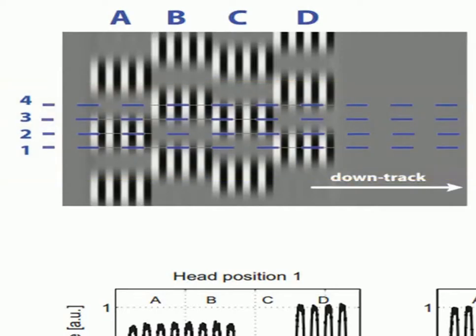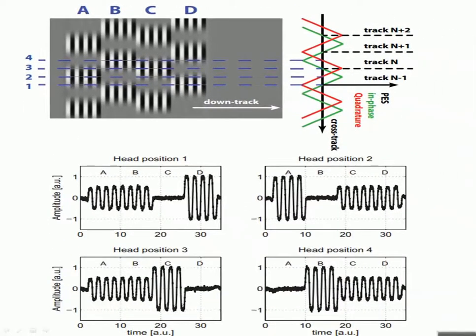Notice that when the head is on track, positions 1 and 3, the bursts A and B start exactly at the center of the track and span radially opposing each other. In position 1, track N-1, C is off track and the middle of D coincides with the track. Whereas in position 3, track N, D is off track and the middle of C coincides with the track. This arrangement is fundamental in how the head position around the track is found. For that, we need to understand the signal that is picked up by the read/write head.